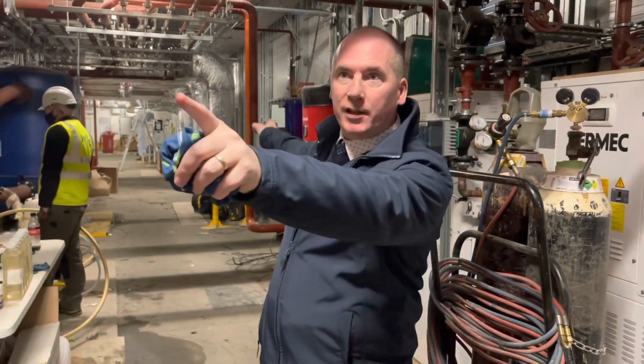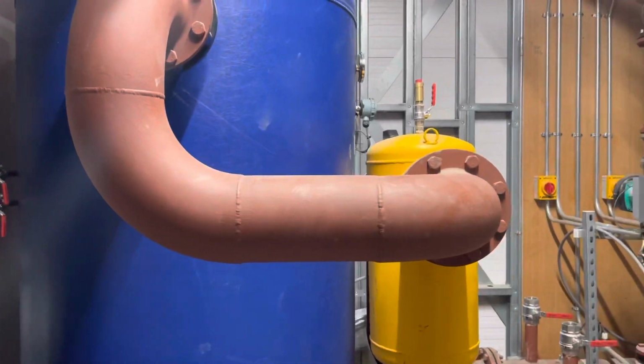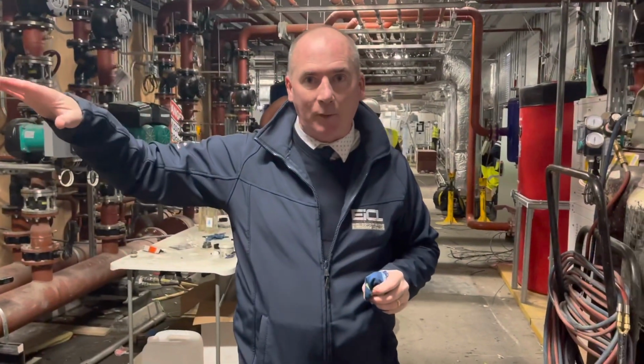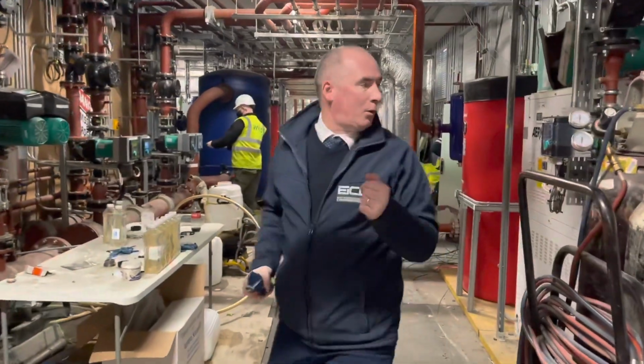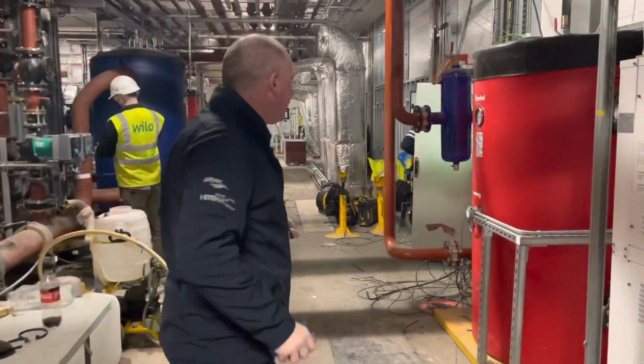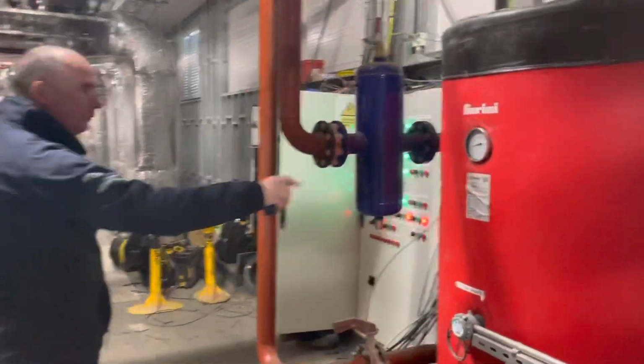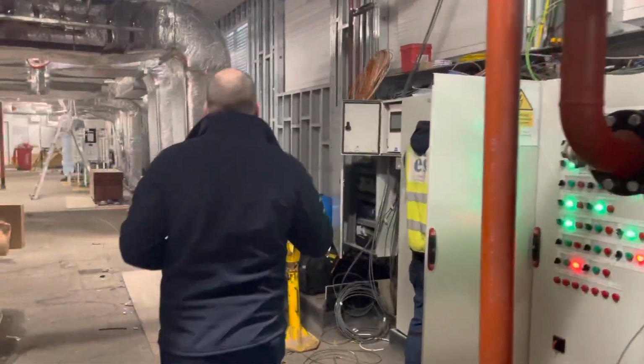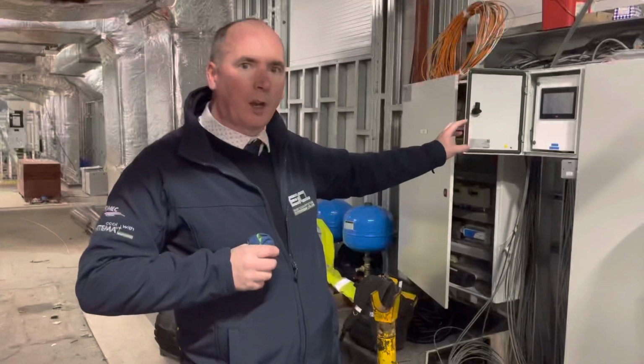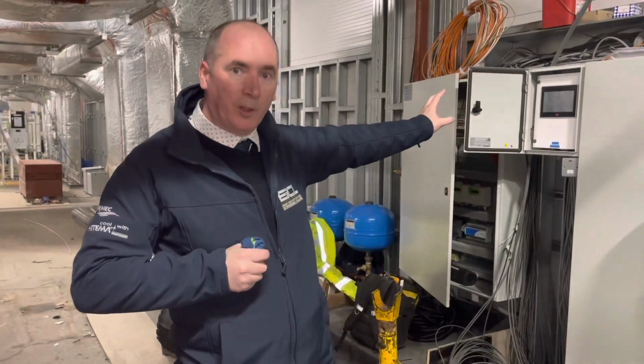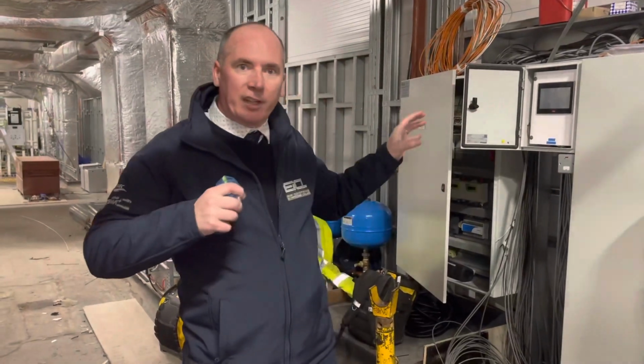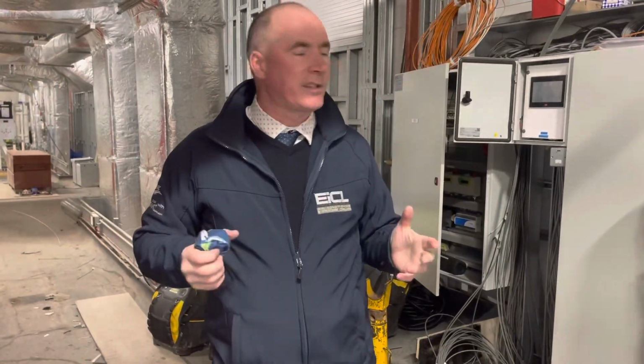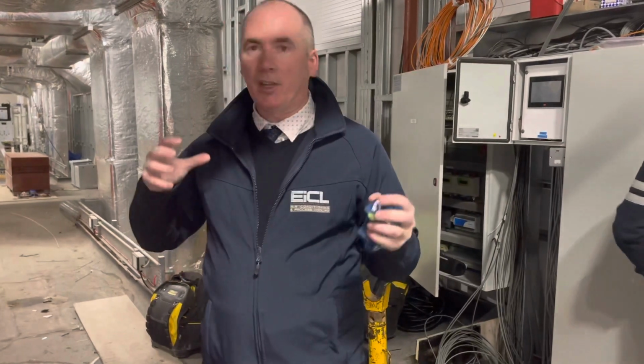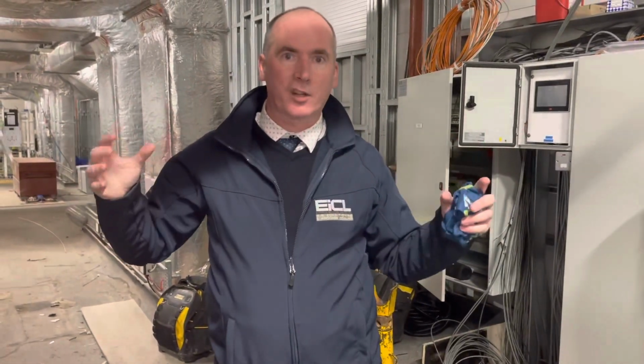So we have a couple of buffer tanks here from Fiorini. These are manufactured specifically, as I said, with the baffle plates to direct the water. And then if you just follow on down here, we have a couple of clarifiers also from Fiorini. So we go in here, and then the rest down there. These are being managed by the multi-unit sequence controller, which is what we have here. As I said, that's programmed specifically to optimize the efficiency of the multifunctional heat pump or the chiller or the other heat pumps. So it's a very, very efficient system, and it's a great solution in relation to all the different combination of products that are all in the one.